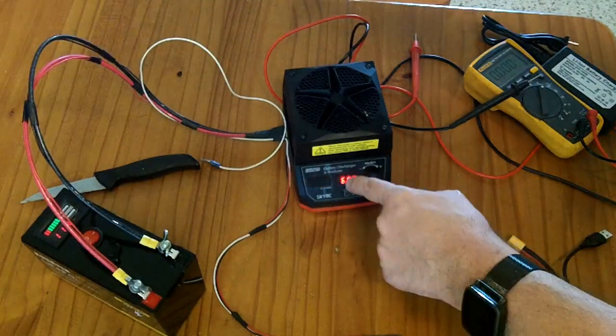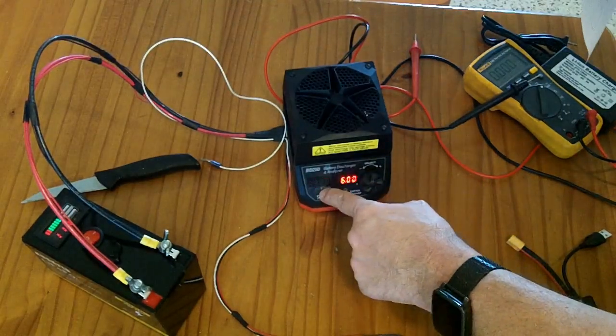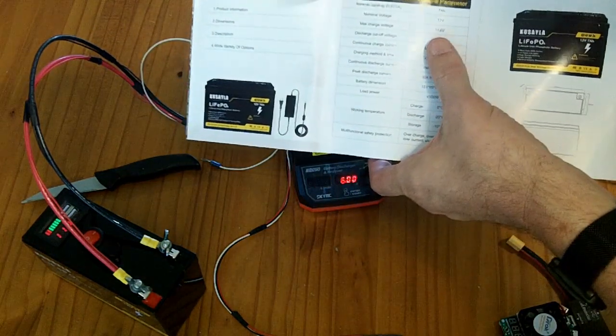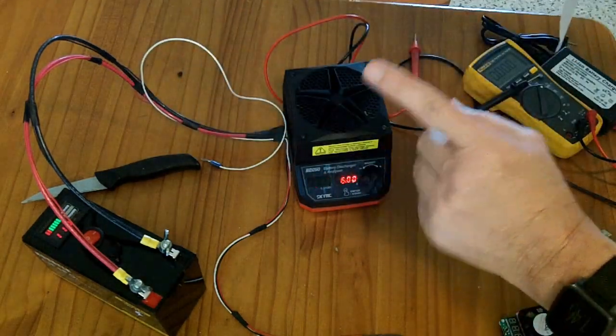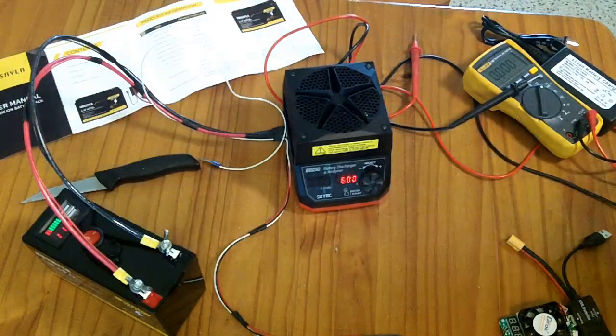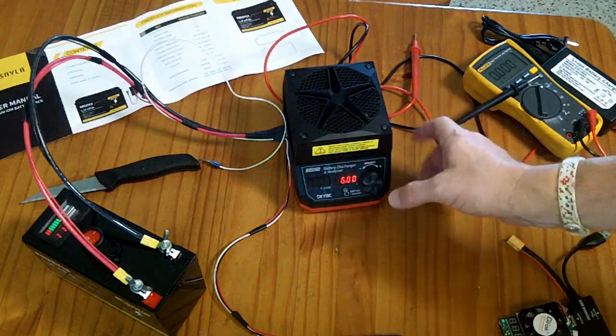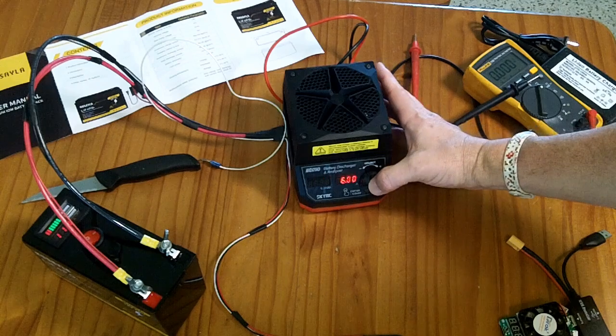I've attached this to a battery discharger, set to draw 6 amps until the battery gets down to 9.5 volts. According to this, the discharge cutoff voltage is 10 volts, so it should automatically cut off before this unit shuts itself down.